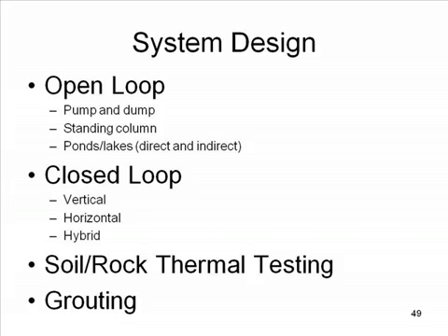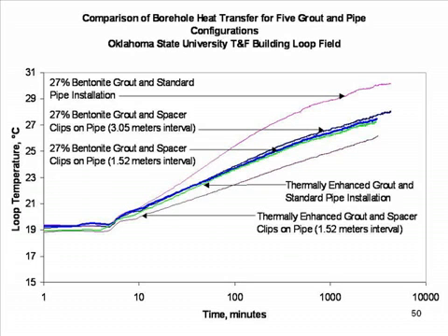And then grouting of the borehole, because you want good contact between the plastic pipe and the formation. This is a slide that we'll get into in greater detail later on in the course. Dr. Smith will be talking about that. Each one of those curves has a different treatment between the pipe and the borehole and the formation. The lowest curve on the page is the best, and you can get that by using thermally enhanced grout and spacer clips on the pipe. And the top one up there is you just bore the hole into the ground and backfill it with a bentonite grout and a standard pipe installation. So the lower the curve, the better, because that's the lower temperature rise that you would get.